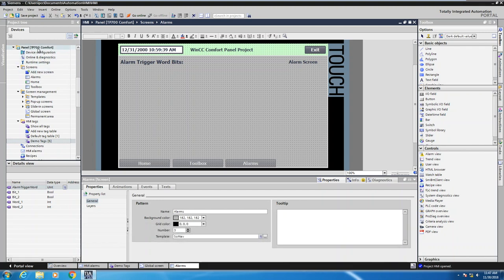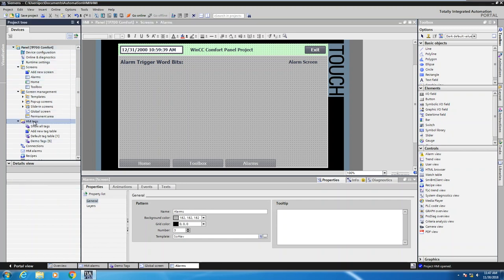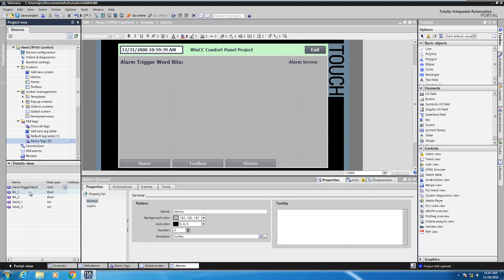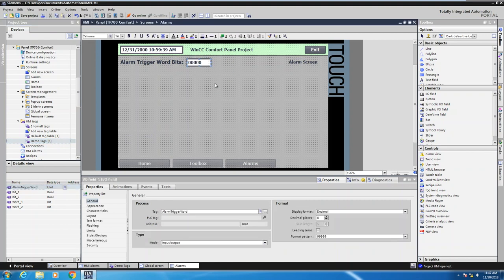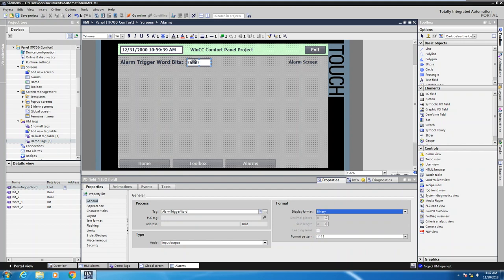In my project, I have a TP700 comfort panel. I'm going to go down to the HMI tags area and look at the demo tags. I have a tag table with a word tag that will allow me to trigger my alarm conditions. In the HMI, you need a 16-bit word tag so you can pick bits out of it — with a 16-bit word tag, you can configure 16 individual alarms per tag. I'm going to drag the alarm trigger word out onto the screen, which automatically assigns it to the IO field. I'll come over to the format area and change the format from decimal to binary, so during runtime I can enter four ones to trigger my four alarm conditions.